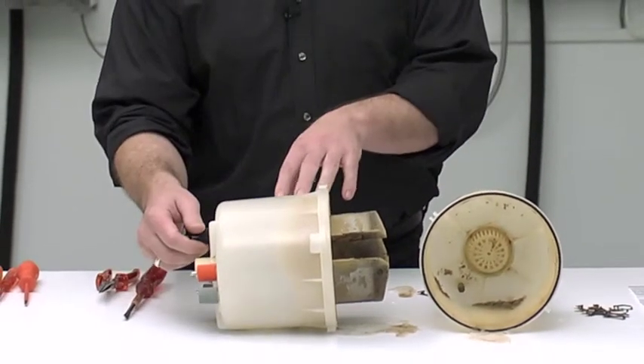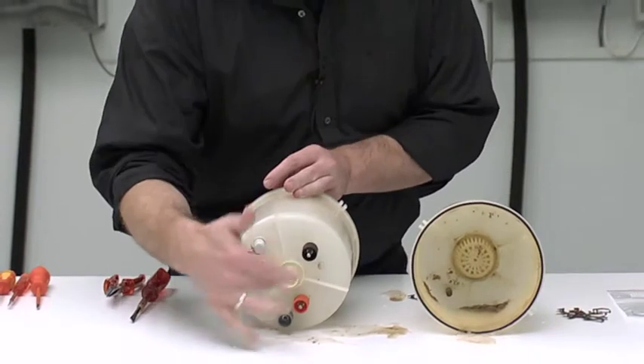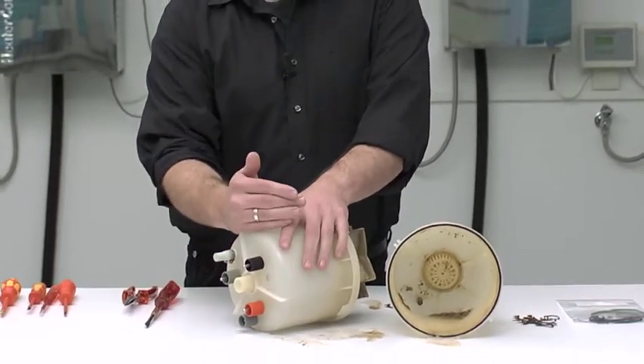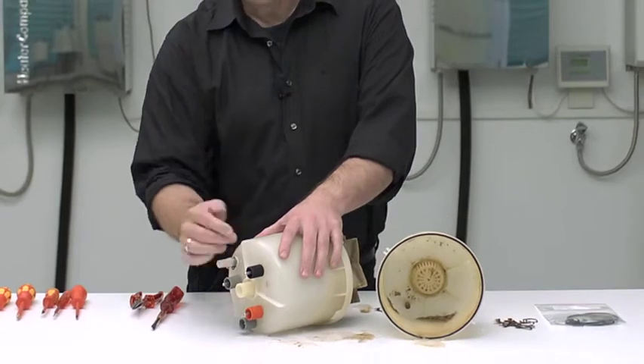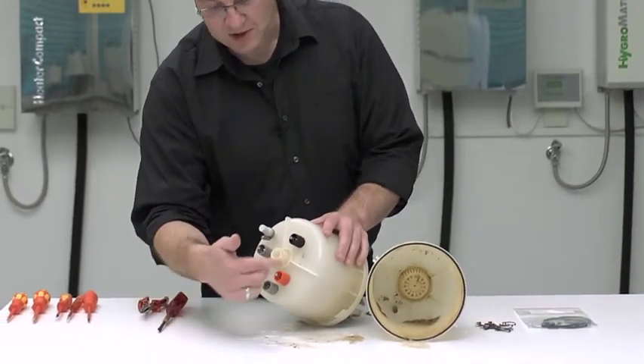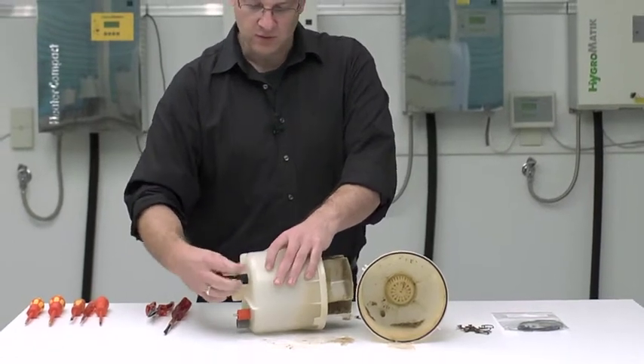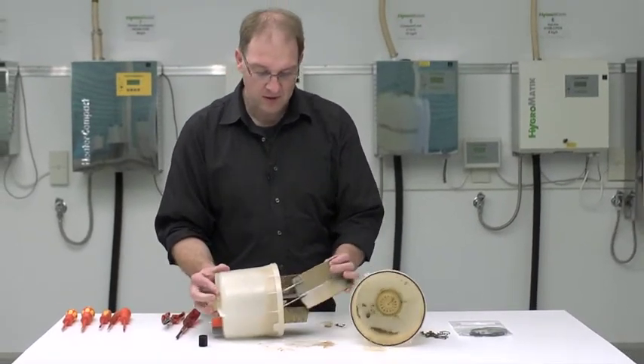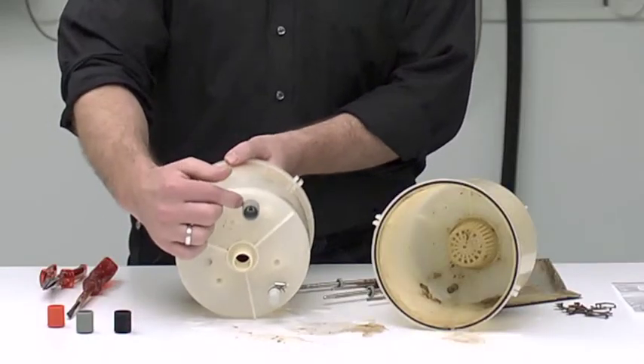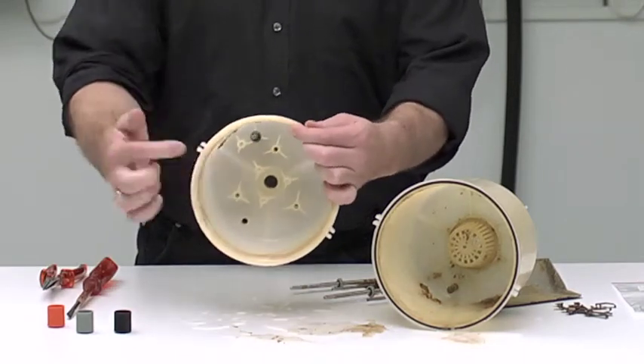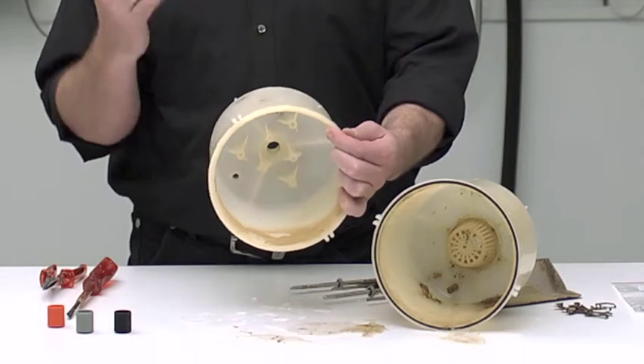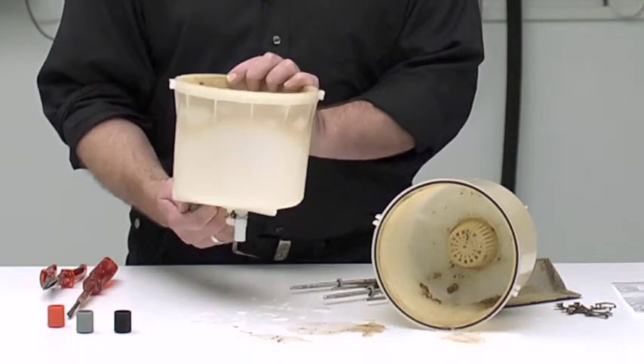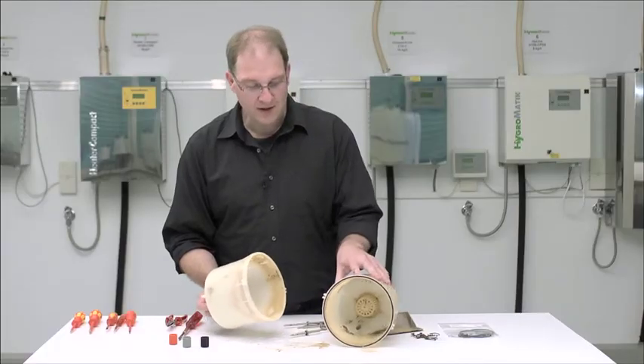Well, disassembly of the electrodes is relatively simple. We've got our knurled nuts all differently colored. This is currently a small steam cylinder with three electrodes. With the larger steam cylinders, from which we want to get more steam output, we would have six electrodes. The larger ones would have two black, two red, and two grey electrodes. Well, this knurled nut can be loosened simply by manual force. Then press to the front, and you can see that there is another one, which is the sensor electrode, which is just a small metal pin that can determine the maximum level of water in the cylinder. This electrode does not wear down and does not need to be replaced, but you should disassemble it and include it in the cleaning.